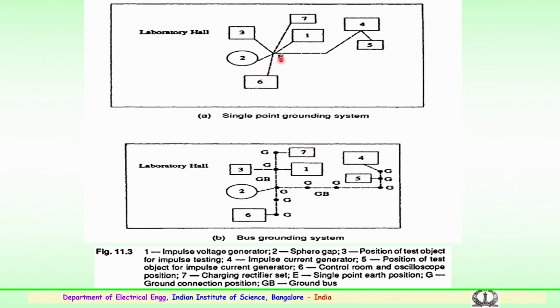You can see all the equipments are connected to a single point earthing connection, where the numbers shown here could be the impulse voltage generator, a spark gap or a sphere gap, the position of the test object for impulse test, the impulse current generator, the position of the charging rectifier set. So, all are connected to a single point grounding here. Similarly, here it is shown connected through a bus grounding system. GB is the ground bus which you see here, and G is the ground connection position at different locations. All the equipments, again the impulse generator, sphere gap, current generator, AC transformer set, DC, several of these things in a laboratory hall are connected by using the bus grounding or the ground connection positions shown here.